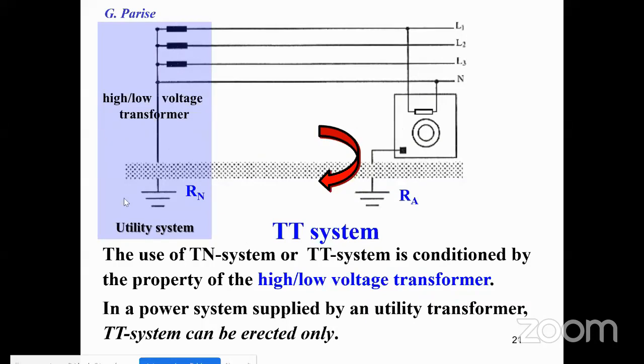The use of TN system or TT system is conditioned by the property of the high/low voltage transformer. So in a power system supplied by a utility transformer, only a TT system can be erected. It's mandatory to adopt the TT system. In the TT system, the exposed conductive part of this washing machine has to be connected to a local ground system.